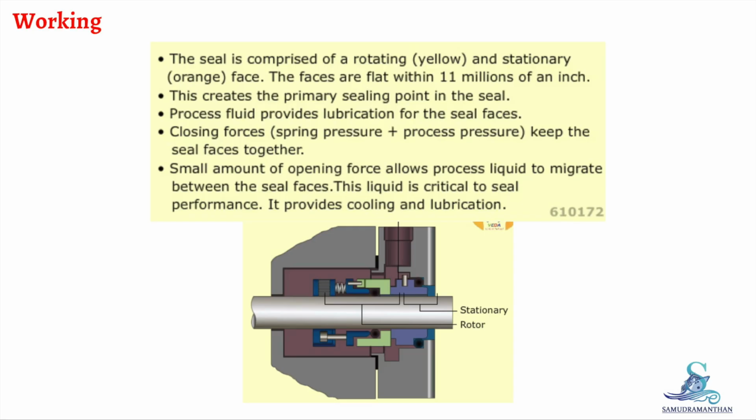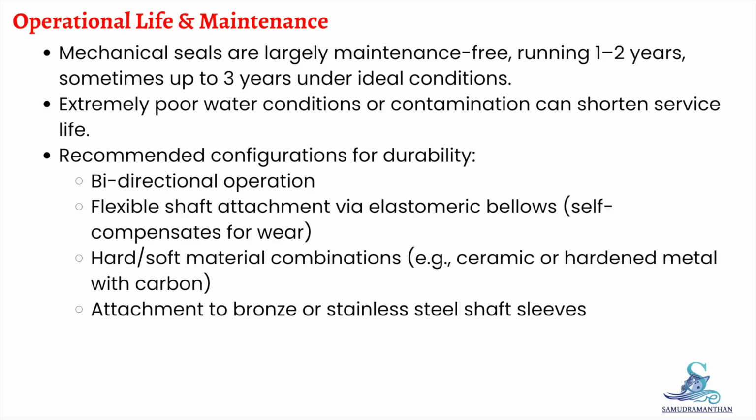Closing forces, which is the sum of spring pressure and process pressure, keep the seal faces together. A small amount of opening force allows process liquid to migrate between the seal faces. This liquid is critical to seal performance. It provides cooling and lubrication.